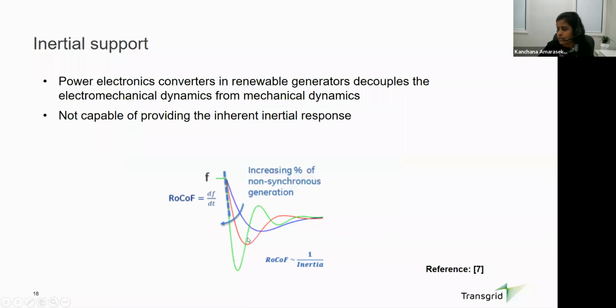I will explain this a bit more with this figure. As an example, let's say a generator trips in a network and the frequency starts dropping. What inertia does is control this initial rate of change of frequency. It holds the network during that initial period until other frequency control services manage that frequency disturbance. But that initial rate of change is controlled by system inertia. And when non-synchronous generation increases, we could see large rates of change of frequency. What it means is sometimes, even before other services can start responding, the system could go to instability if we don't manage the rate of change of frequency. So this is about inertial support.